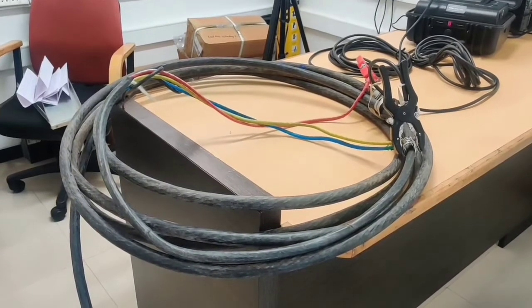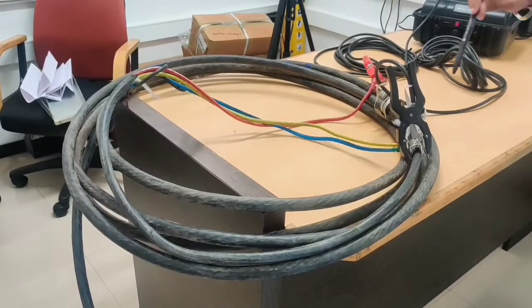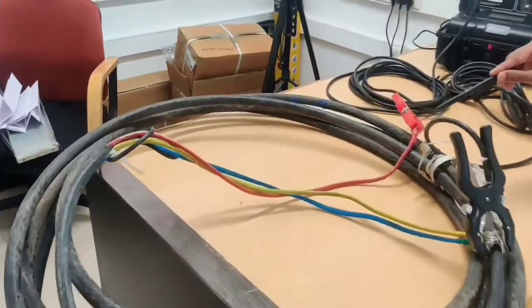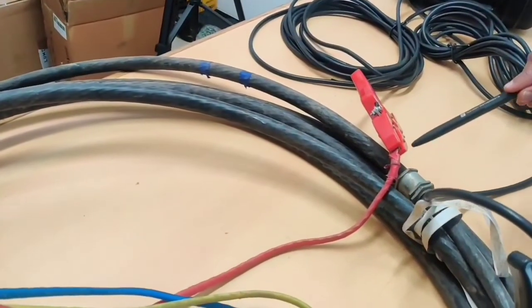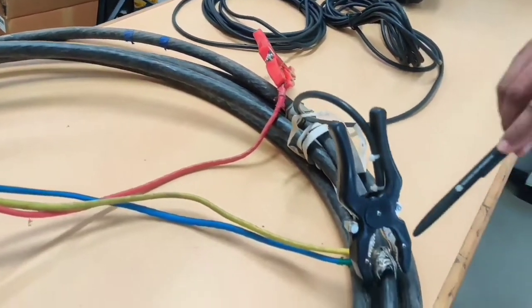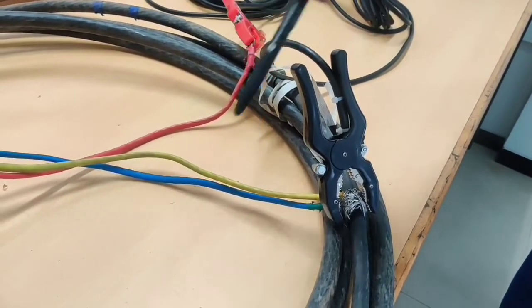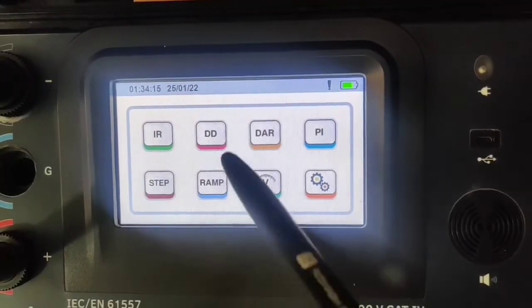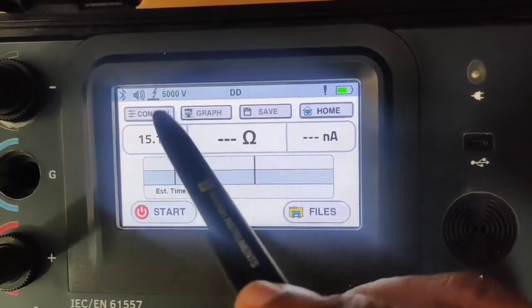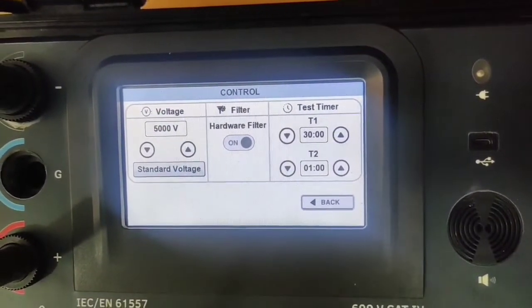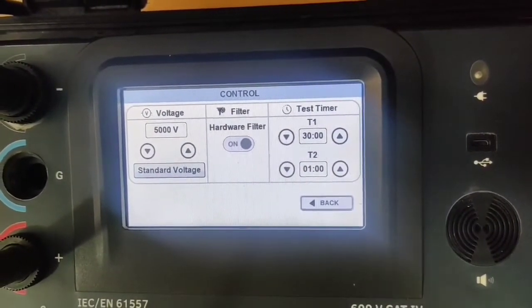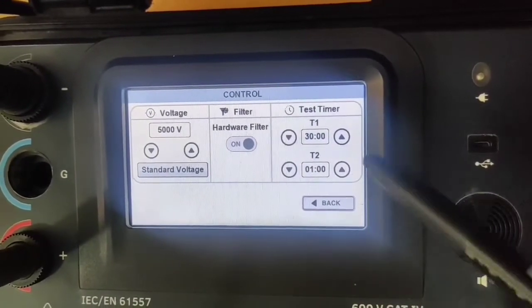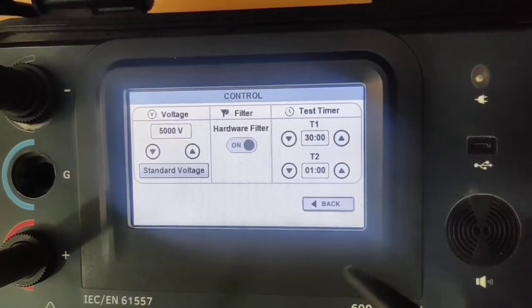Now we will perform the dielectric discharge test on a three-phase cable. As you can see, it is a multi-layer cable. We have done the line connection to the R-phase of the cable, and the return connection by shorting Y-phase, B-phase, and the insulation body of the cable. We will go into the DD test parameters and set the test voltage to 5000 volts. For the DD test, you need to set two timers, T1 and T2, for 30 minutes and 1 minute, as you can see on the display.